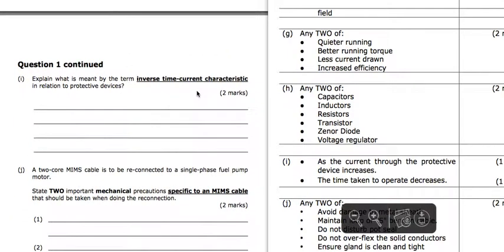Inverse time current characteristic. Again, we've seen this before, and it's all about the bigger the current that flows through a protective device, the quicker that it's going to operate. So as the current through the protective device increases, the time taken to operate decreases. So it's inversely proportional.